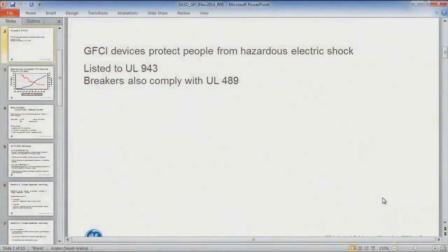I brought some samples. So the question was, is there a UL standard that includes both the circuit breaker protection as well as the shock protection, ground fault protection? And there are two ways to protect people from shock in NEMA applications. One way is to combine the shock protection along with the circuit breaker. Brad, can you please hand him that two-pole device? So the two-pole device with the red trip button is a two-pole circuit breaker that has integral shock protection built in. So it's a ground fault breaker as well as overcurrent protection together.